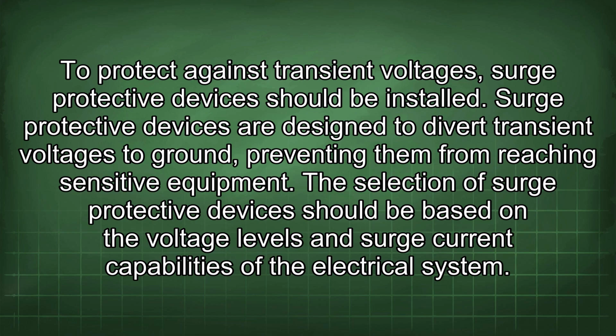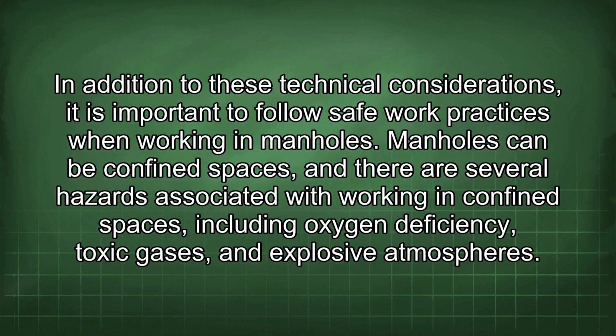To protect against transient voltages, surge protective devices should be installed. Surge protective devices are designed to divert transient voltages to ground, preventing them from reaching sensitive equipment. The selection of surge protective devices should be based on the voltage levels and surge current capabilities of the electrical system. In addition to these technical considerations, it is important to follow safe work practices when working in manholes.